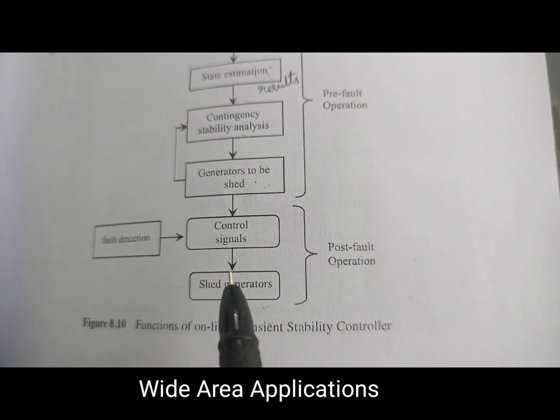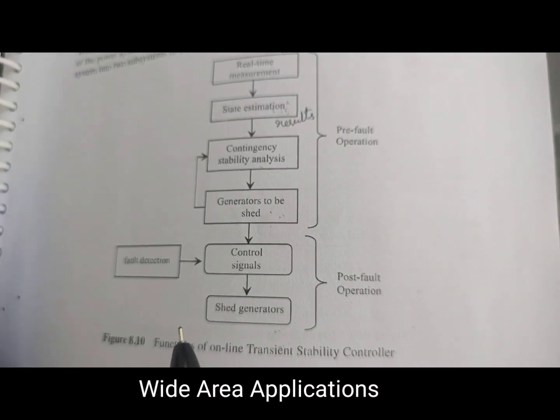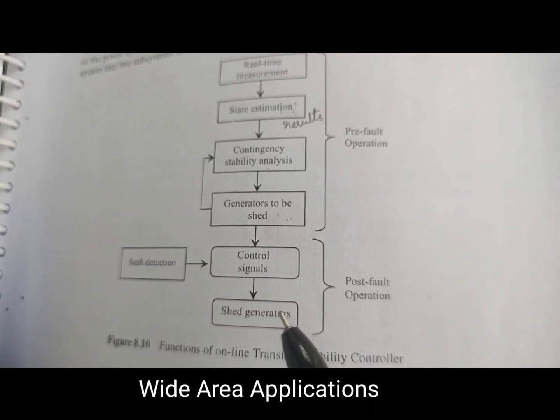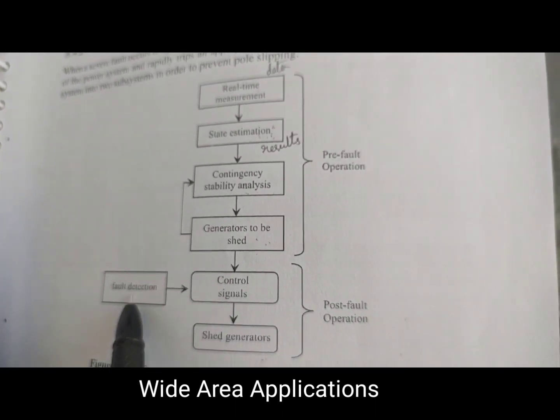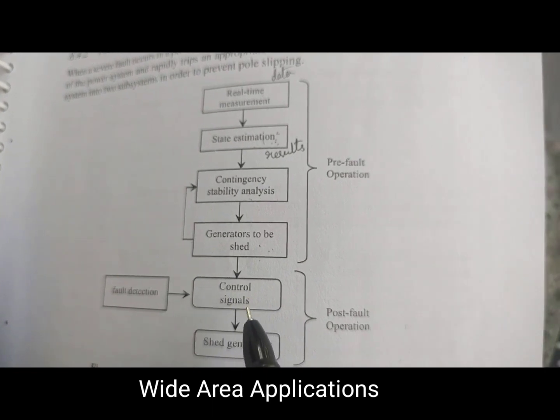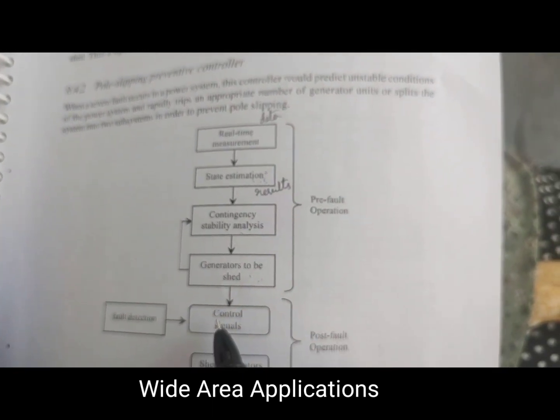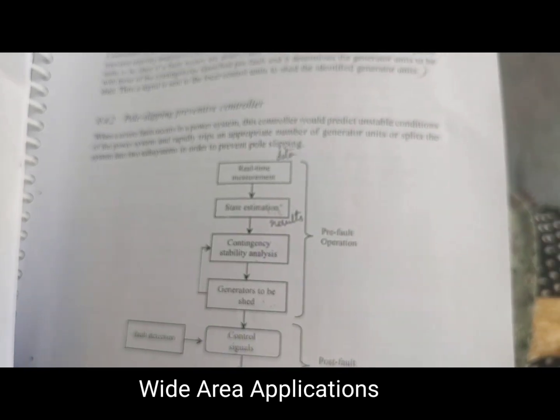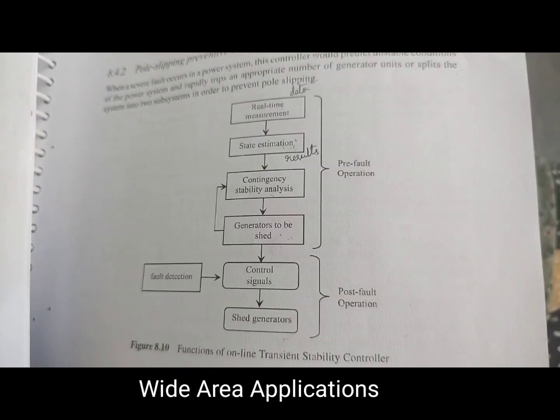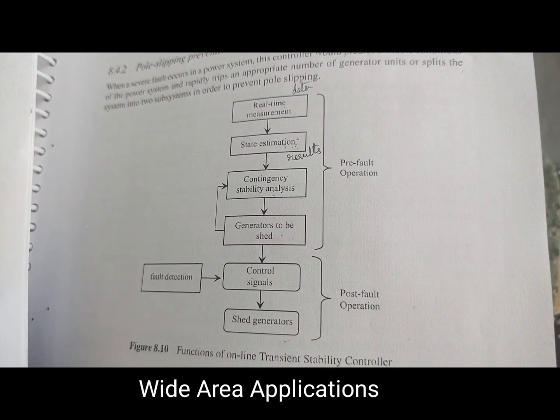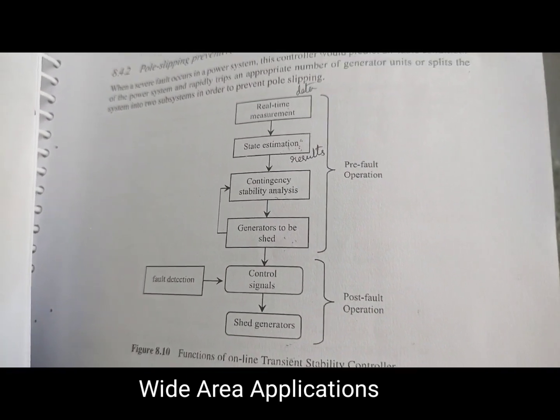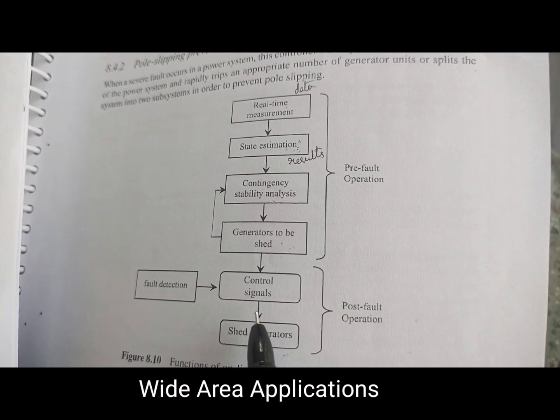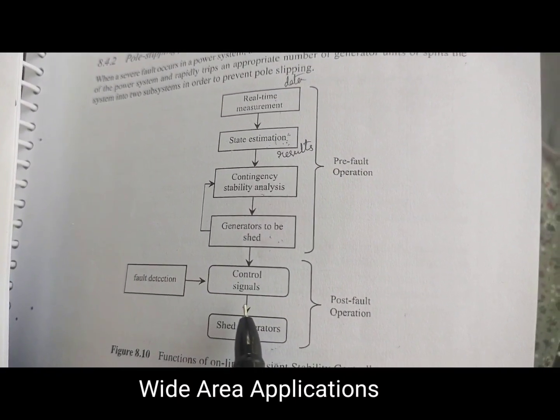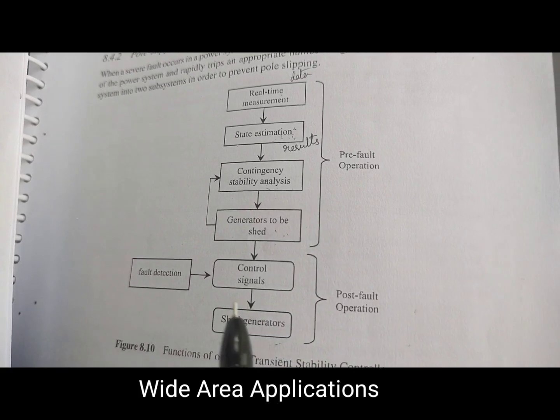After a fault occurs, the fault is compared with the contingencies identified before. It will determine the generator units to be shed. Then a signal is sent to the local control units to shed the identified generator units.